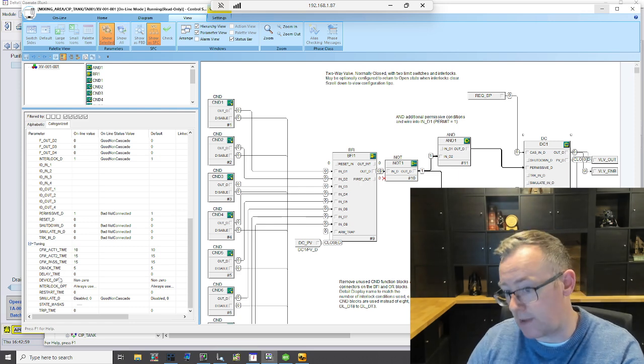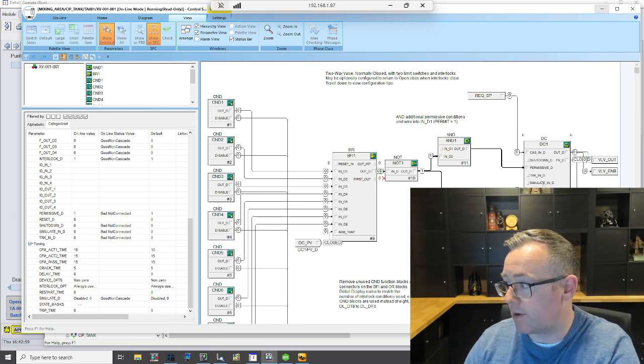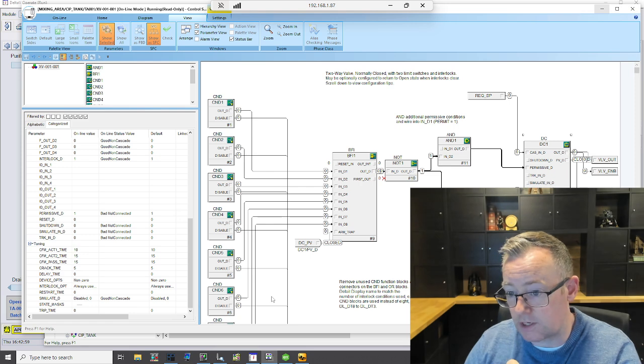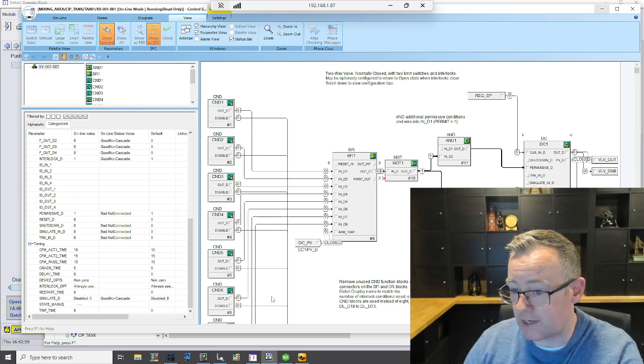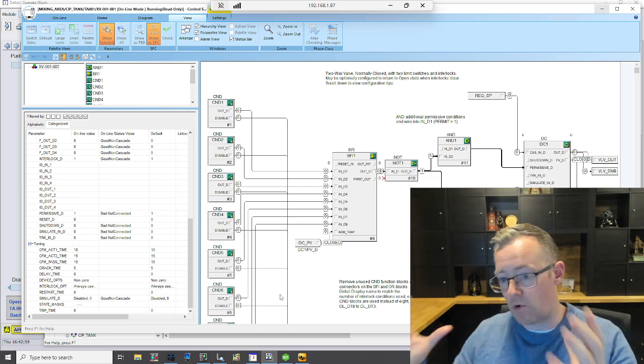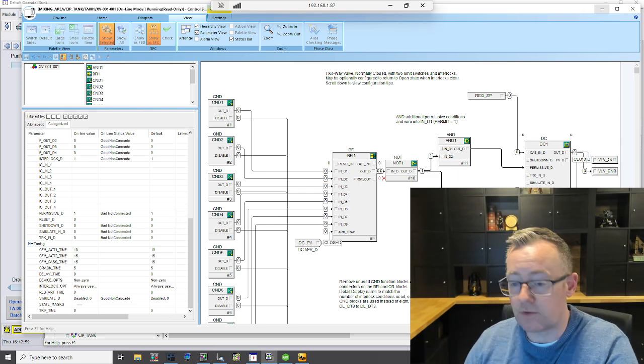be tweaks made to the variables over time. For example, if you look at the simulate input here, you'll effectively find that you might have lots of interlock conditions going on, but those interlock conditions are not actually being challenged when they actually should be challenged. So that's why I feel that a broader audience should definitely have an understanding of these things here.